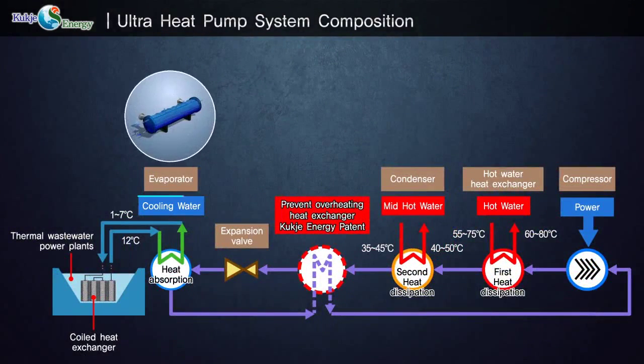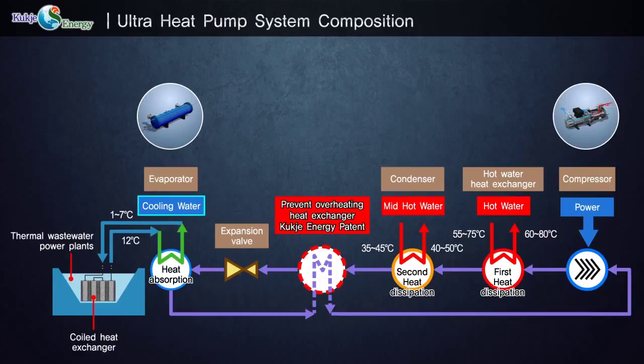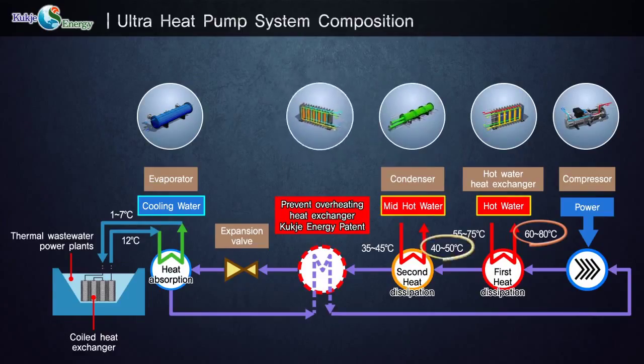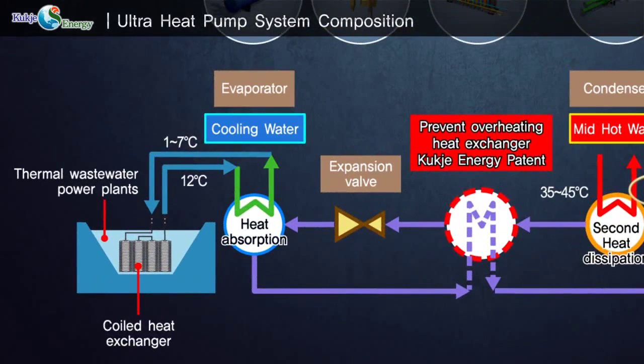consumption. The ultra heat pump absorbs thermal wastewater heat from power plants to simultaneously generate high-temperature water of 60 to 80 degrees Celsius in the hot water heat exchanger and medium-temperature water of 40 to 50 degrees Celsius in the condenser. If cooling is required, it can provide cold water at 1 to 7 degrees Celsius. Since a sealed heat exchanger is submerged in the drain under the power plant to exchange only heat, it is possible to utilize the heat without polluting the seawater.